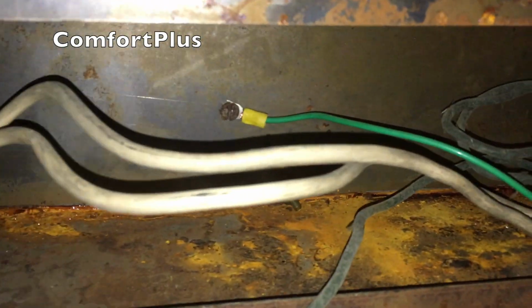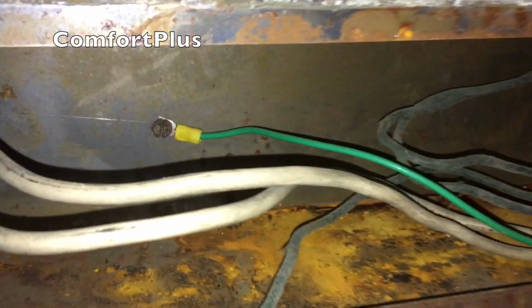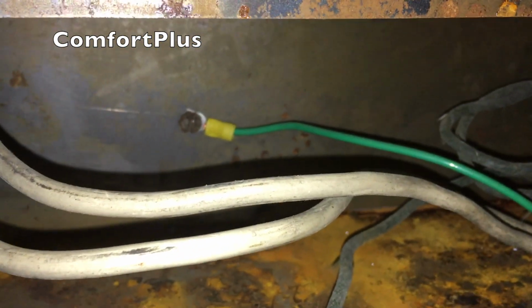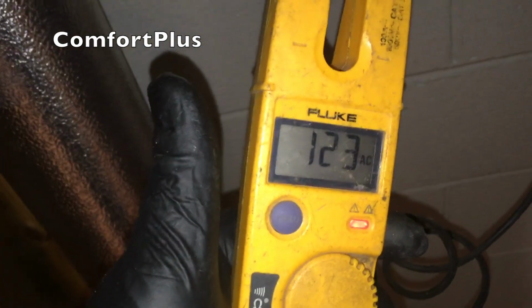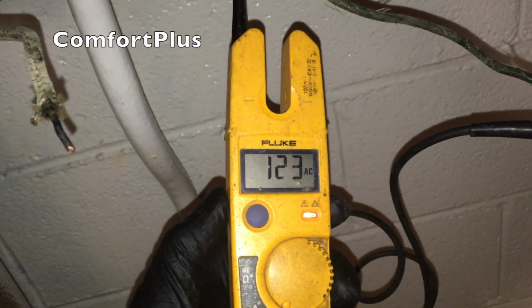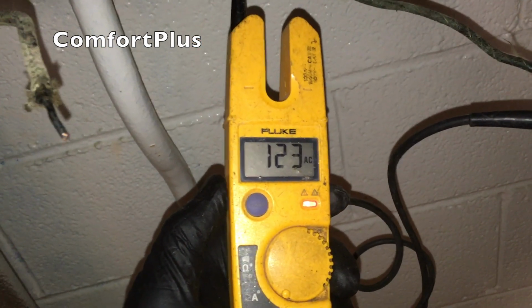Okay, I got to thinking maybe I shouldn't use this old circuit, because they're using the conduit as a ground here for that old unit. I had a newer circuit over there that had been run to a little panel up on the stage. This one comes from down in the boiler room. But of course you can see I have my 123 volts to the neutral, but I also have 123 volts to ground.